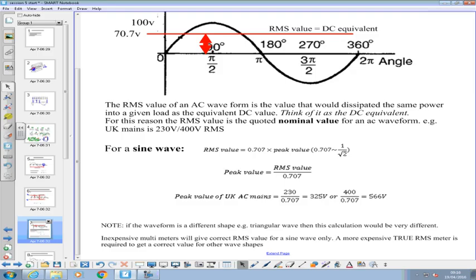Inexpensive multimeters — your 70 to 100 pound jobs — will measure the correct RMS value assuming your waveform is a perfect sine wave. If you want the RMS value for any wave shape, you need to buy a more expensive true RMS meter, costing 500 to 700 pounds, and that will measure the RMS value of any waveform. You'd only spend that extra money if you're working with unusual wave shapes regularly. You can always use an oscilloscope to measure the peak value and derive RMS from there. The RMS is the quoted nominal value of an AC supply.